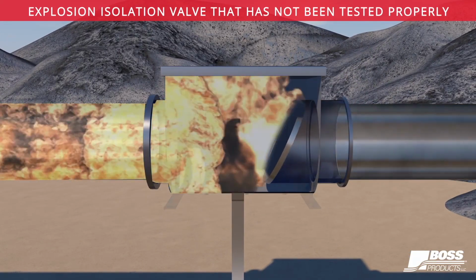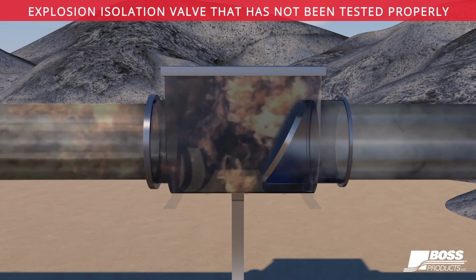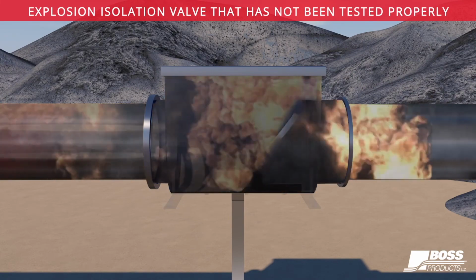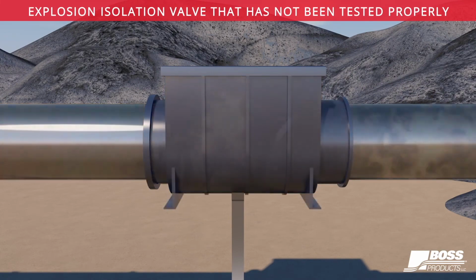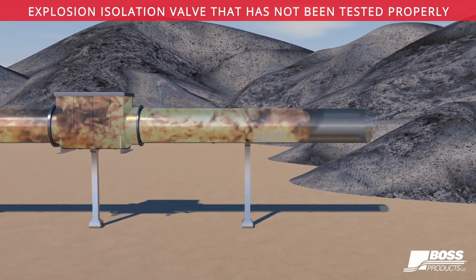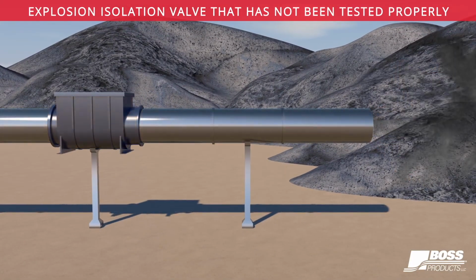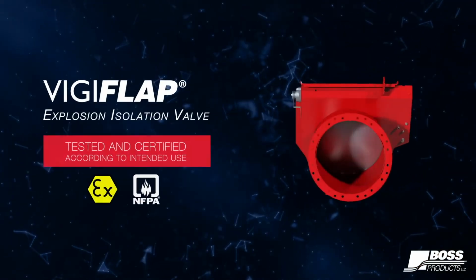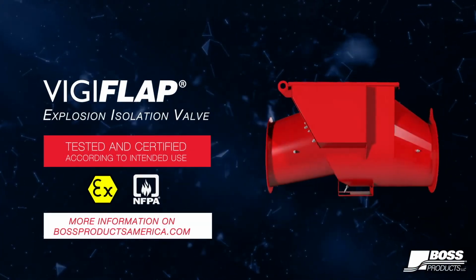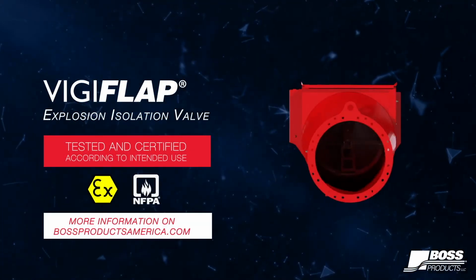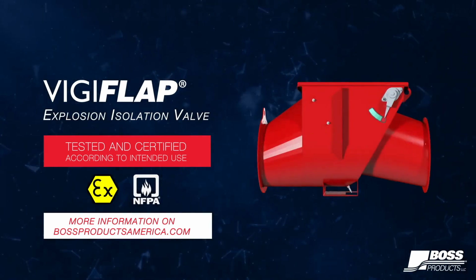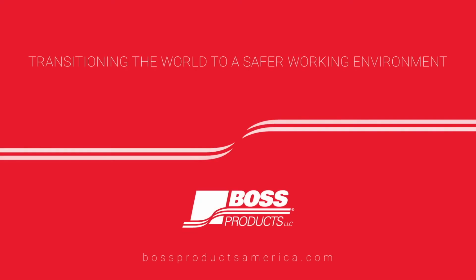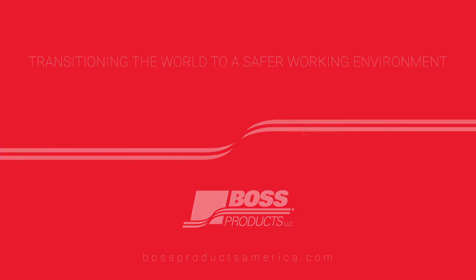There's your pressure wave pushing the flap. This valve wasn't certified in accordance with a secondary pipe with the other side of the pressure, and you get the explosion on the other end. So we offer the VigiFlap, which is our explosion isolation valve. It can be used on both clean and dirty side of the collector or the vessel that you're protecting.